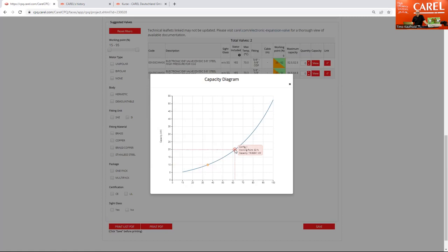And here you can see where you're going to be. What is this valve doing, and is everything fine? I suggest every one of my customers use 3 points: minimum, maximum, and anything in the middle, to see where you really are. Because many people think, hey, it's an electronic expansion valve, you never get problems like hunting or anything like this. Wrong, totally wrong.